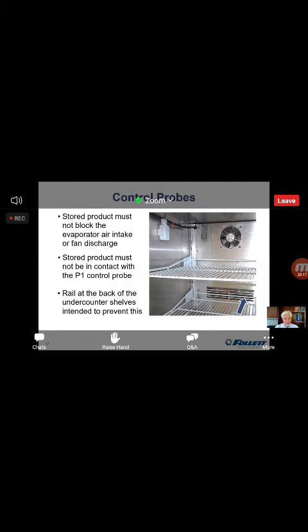Well, number one, it blocked the airflow. Number two, we had product laying on top of the probe, and so we lost control of the refrigeration temperature. So just be alert to that, okay? The other thing that I like to remind the staff, and occasionally it does require a general reminder, you can't store 5 cubic feet worth of product in a 5 cubic foot refrigerator or freezer. That's simply not going to work. You need to allow the air to move around it. If you pack it totally full, it's going to have a hard time maintaining accurate temperatures, all right?